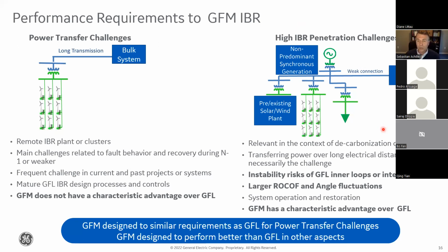So this problem on the right is not related to pushing power through a weak connection. It's more related to keeping the system stable in terms of other aspects beyond transferring power. The problem on the left is the old problem, I would say, but we still have it. The problem on the right is the new problem. In the field, we tend to see combinations of the two. From the point of view of performance requirements, it makes sense that grid forming has performance requirements that go way beyond what grid following is asked to do for problems related to the system on the right. We don't expect that grid forming products are going to perform significantly better than grid following, at least advanced grid following, for the problem on the left.